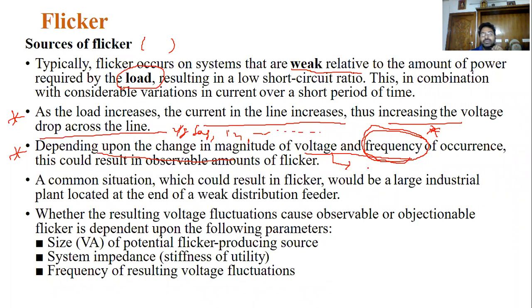Okay. So in the voltage sags, swells and interruption case, most of the time we assume it as a time as well as the number of cycles present in the system. Now see this: in flickers, we can assume the magnitude of the voltage. At the same time, you can assume the frequency range. What is that frequency range? 0.5 hertz to 30 hertz. But in voltage sags and swell cases, we can assume it as a number of cycles from 0.5 cycles to 30 cycles.